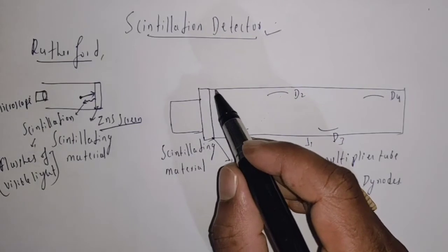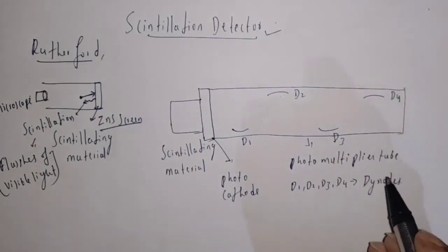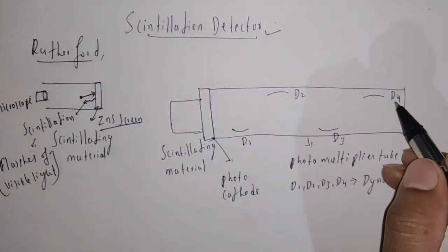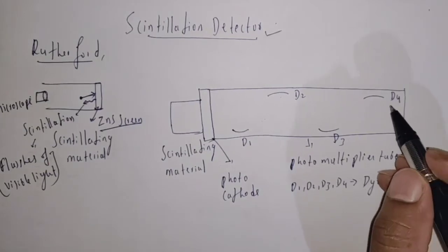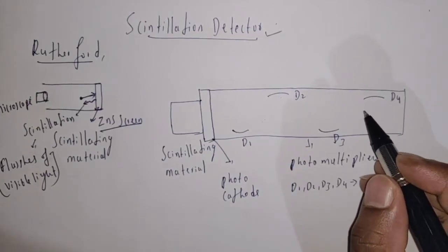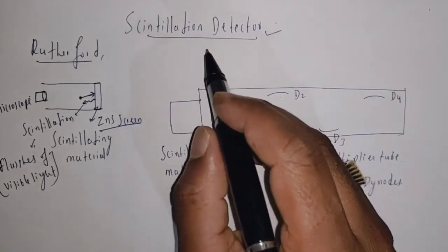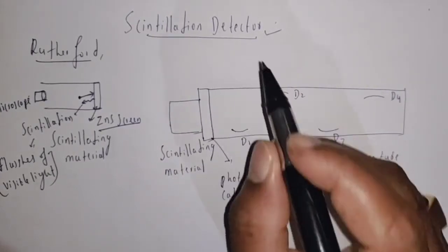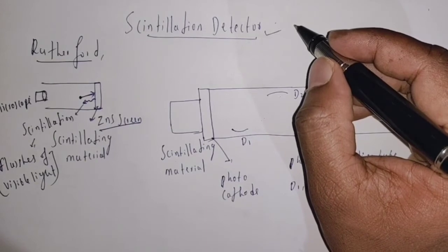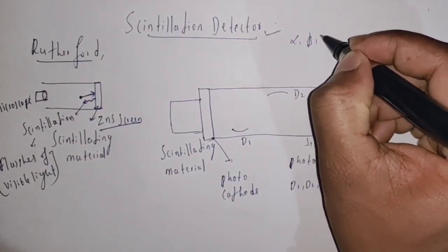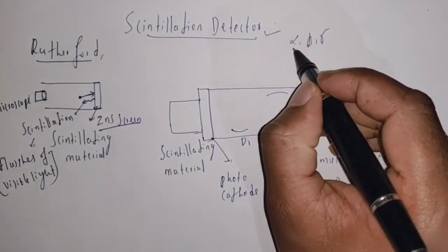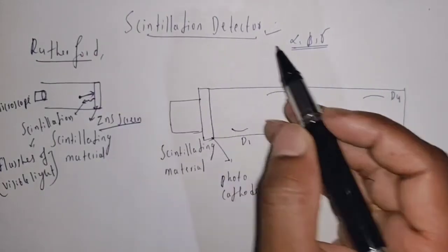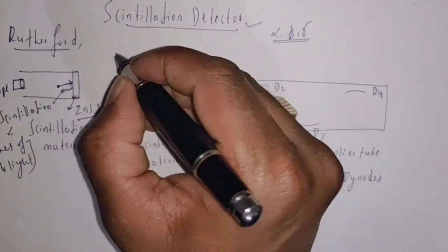The cathode is attached to the photomultiplier tube and this photomultiplier tube consists of dynodes D1, D2, D3, D4. This is all about the construction of the scintillation detector. This scintillation detector is used for the detection and measurement of nuclear radiations such as alpha, beta, and gamma radiations.